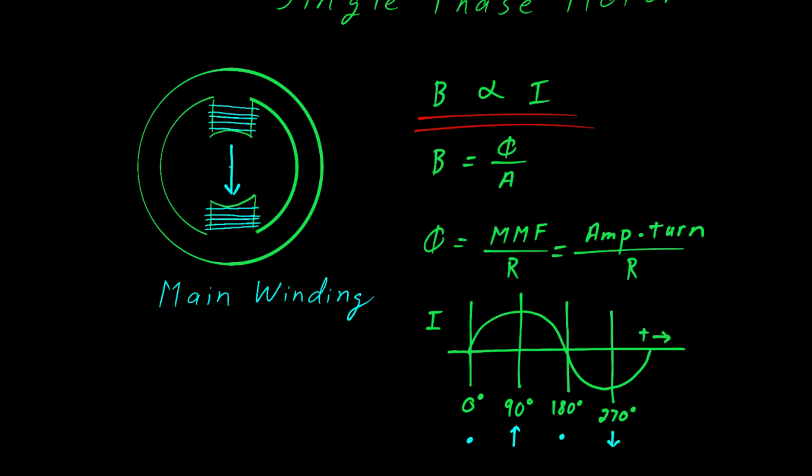This vector is certainly not rotating. All it's doing is growing up and then growing down. It's growing to the north, shrinking and then growing to the south and then shrinking back. What we need is a second set of windings that will allow us to point east and west and so we add the start winding.